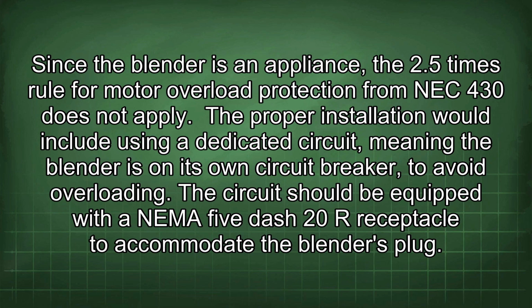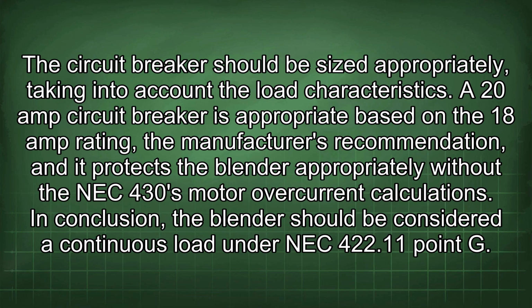The proper installation would include using a dedicated circuit, meaning the blender is on its own circuit breaker, to avoid overloading. The circuit should be equipped with an NEMA 5-20R receptacle to accommodate the blender's plug. The circuit breaker should be sized appropriately, taking into account the load characteristics. A 20 amp circuit breaker is appropriate based on the 18 amp rating and the manufacturer's recommendation, and it protects the blender appropriately without the NEC 430 motor overcurrent calculations.